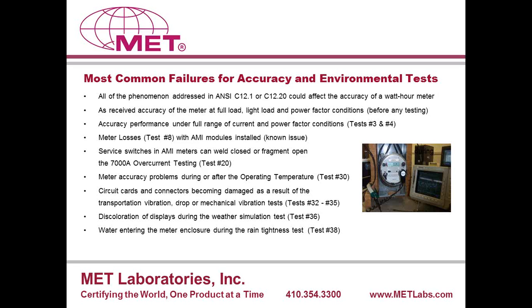Load performance testing, power factor tests, test 3 and 4 out of the ANSI standard, running under the full range of load conditions. Many times you'll see failures at the low end and sometimes even the high end, depending on the rating of the meter. Wireless modules installed on one of the circuits, the one side circuit of the meter, could affect meter losses. Sort of a known issue, but we do see that on occasion.